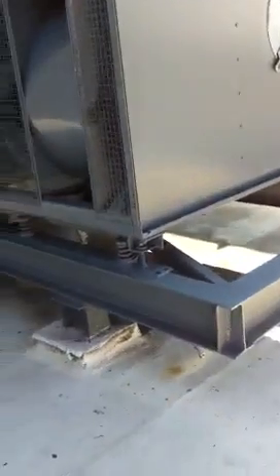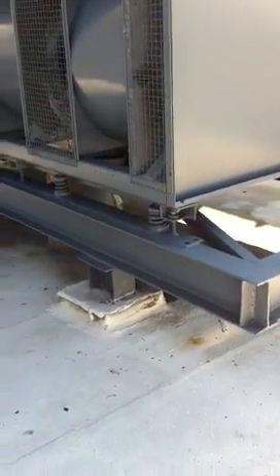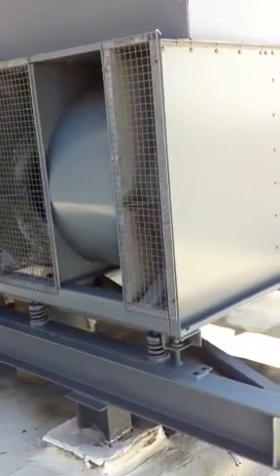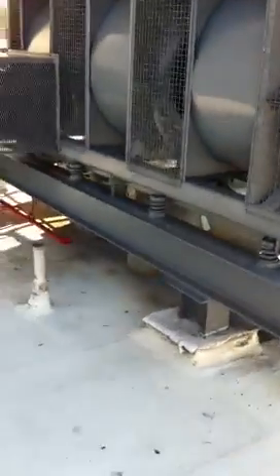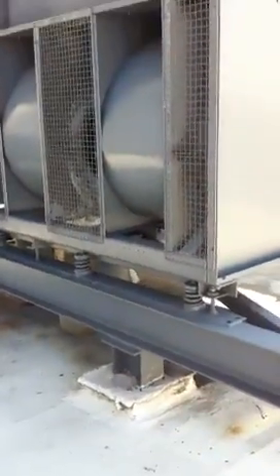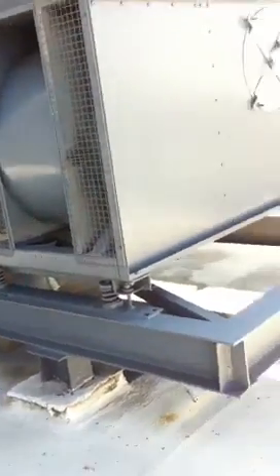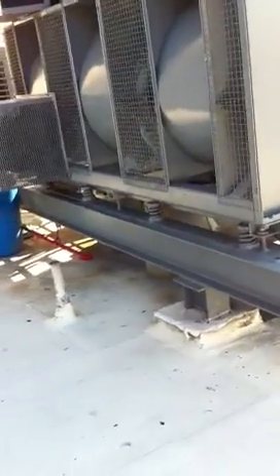Install eliminators within the top outlet section of tower housing as needed. Eliminators are those plastic pieces right there, and basically what those inserts do is they stop water from misting and spraying up in the air. You end up getting calcified water down in your cars and whatnot. That prevents that. So basically you have the main system with this add-on that prevents the calcification and the debris. Remove and replace existing cooling tower expansion tank with matching capacity, so that's that thing there.